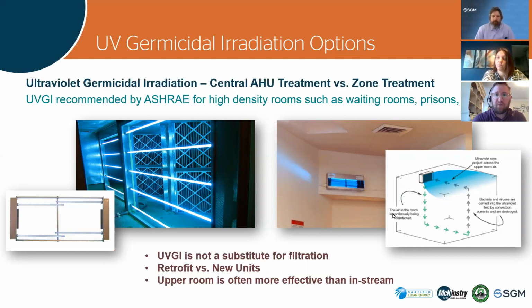And in my mind, this is really something that you're going to use for a special application, maybe a waiting room where you're expecting COVID-19 patients to be a probable source of contaminants. What this is doing is it's not going to be visible to the eyes of occupants. It's going to sit up near, likely, a return grille and treat the air and treat the surfaces of the room as the air returns back to the unit. And it's certainly not a substitution for filtration.